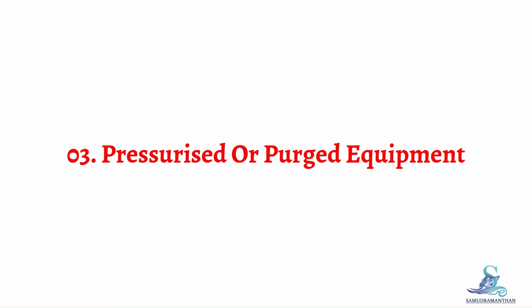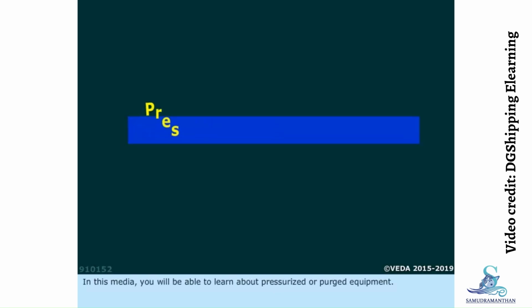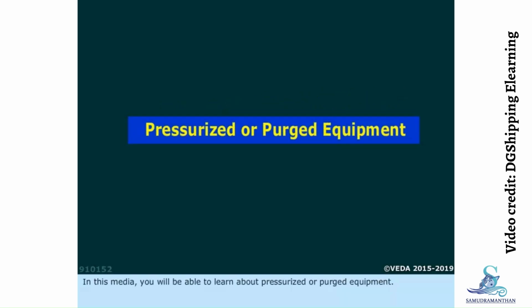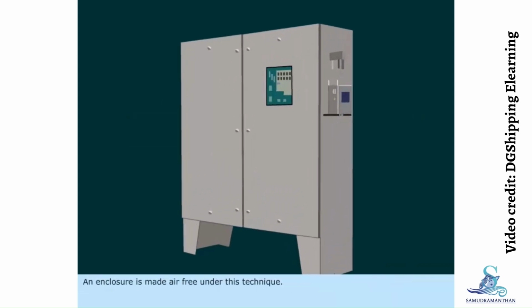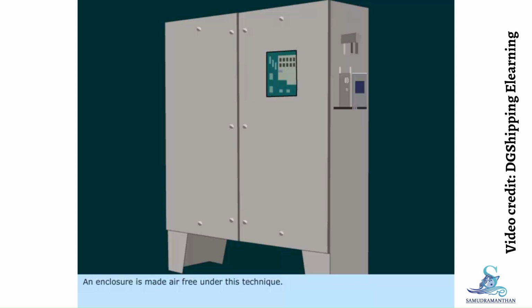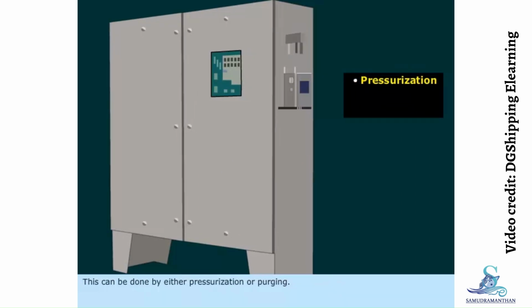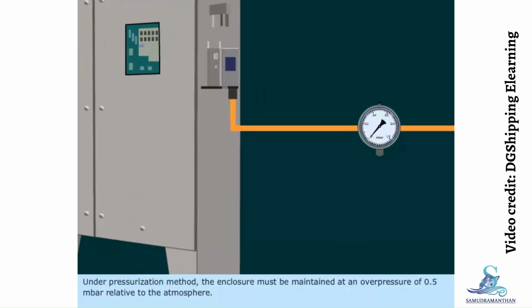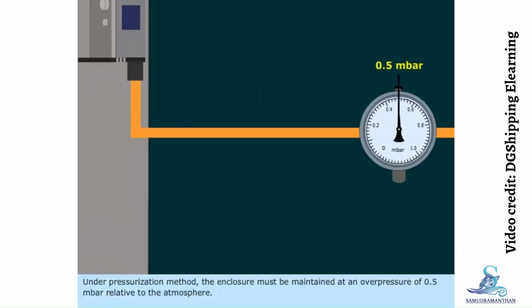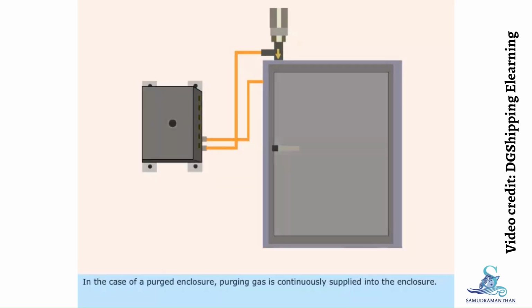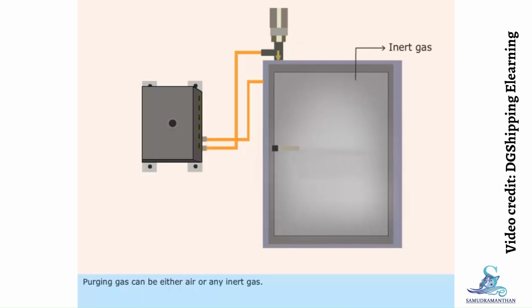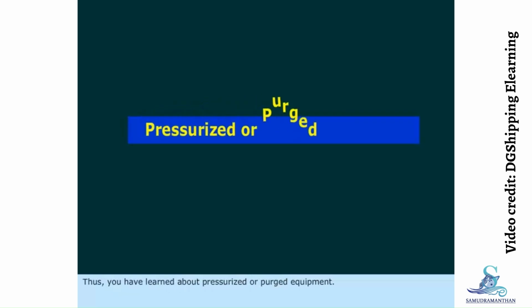Topic 3: Pressurized or purged equipment. In this media, you will be able to learn about pressurized or purged equipment. An enclosure is made air-free under this technique. This can be done by either pressurization or purging. Under the pressurization method, the enclosure must be maintained at an overpressure of 0.5 mbar relative to the atmosphere. In the case of a purged enclosure, purging gas is continuously supplied into the enclosure. Purging gas can be either air or any inert gas. Thus, you have learned about pressurized or purged equipment.